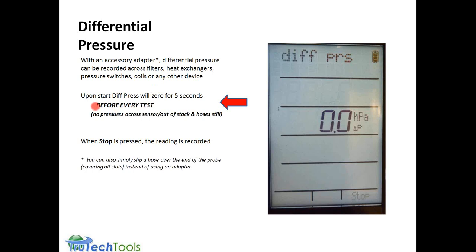Again, it's important to make sure that before every pressure test, there will be a zeroing or a quiet period, in which you have no pressures on the sensors or the hoses, and you keep still for that 5-second countdown. Then when you press the stop button in the lower right-hand corner, the reading is recorded and stored for your subsequent printout.